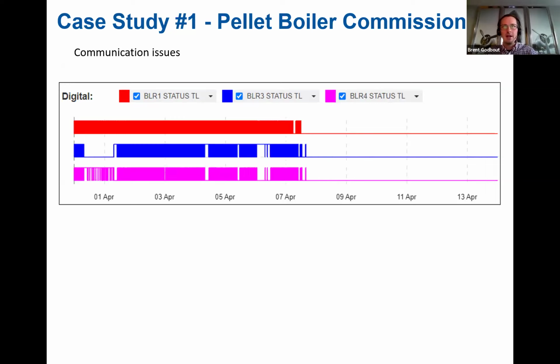And they were just providing enough heat for the heating loop, and our pellet boiler was running, and we were sending heat over to the hospital, and nothing was being exchanged into the heating loop. Took some time to figure it out, but then we eventually did. In March, we actually shut down, so the pellet boiler wasn't running. So this is the oil boilers. You can see here they were firing pretty steadily, and then boom, on around April 8th, we finally figured it out, and the pellet boiler started taking the lead.